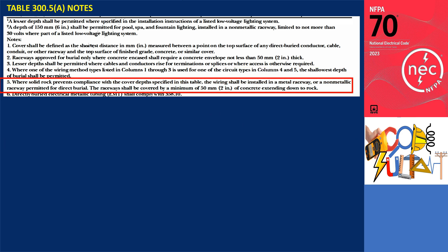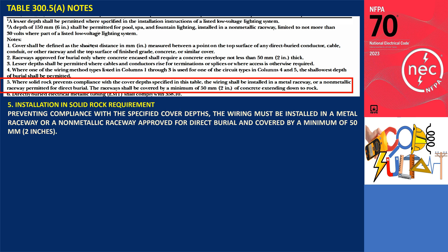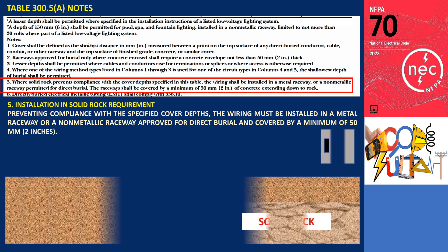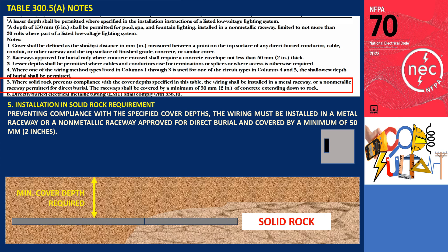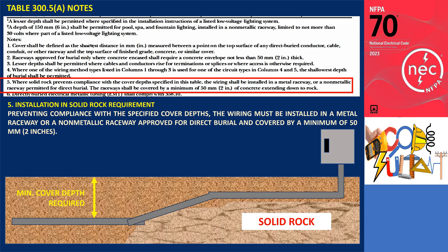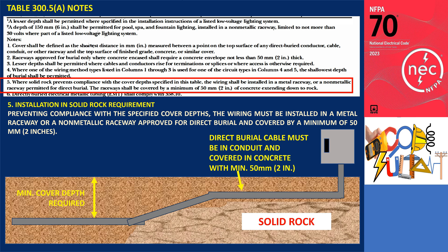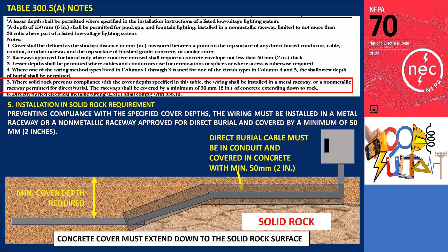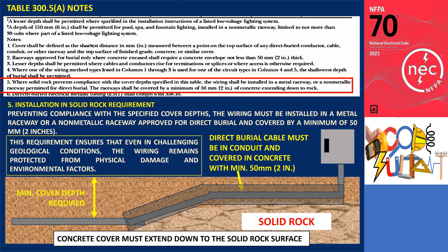Note 5: If solid rock prevents adherence to the cover depths specified in this table, the wiring must be installed in either a metal raceway or a non-metallic raceway approved for direct burial. These raceways should be encased in at least 50 millimeters (2 inches) of concrete that extends down to the rock. When installing a direct burial cable, solid rock may obstruct compliance with the minimum cover depth in Table 300.5(a). Per Note 5, the cable can be buried at a shallower depth but must be placed within conduits and covered by a minimum of 50 millimeters (2 inches) of concrete reaching down to the rock, ensuring protection from physical damage and environmental factors.